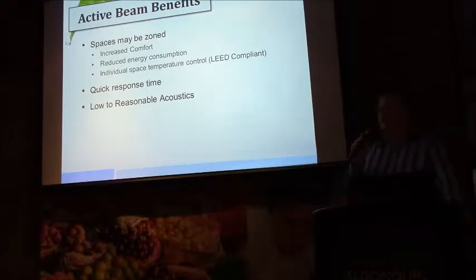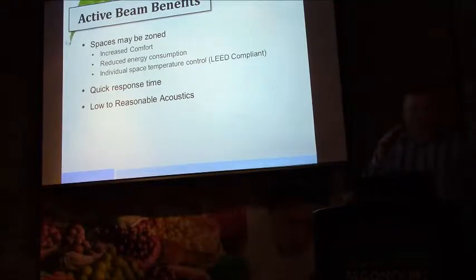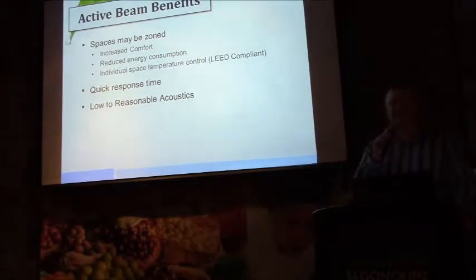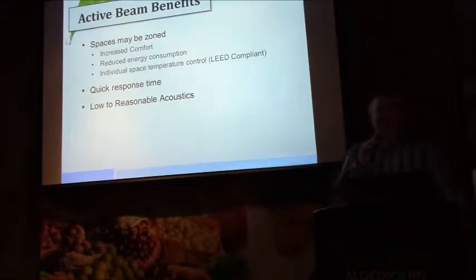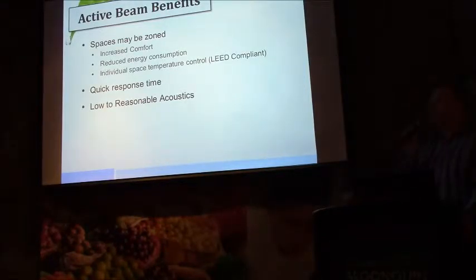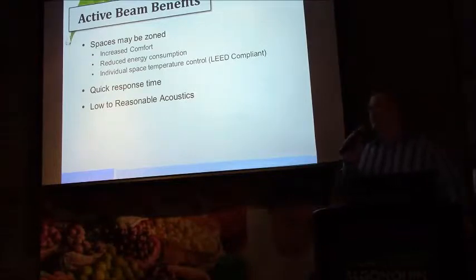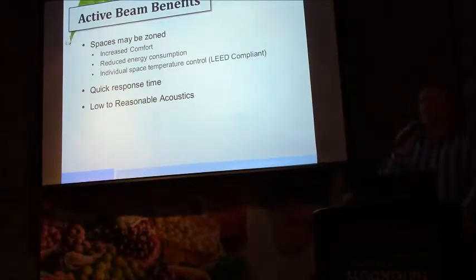And so it's been observed on other projects whereby a competitor came and offered a shorter coil because the capacity of the beam was suitable to accomplish that. But the design criteria of the space was such that the acoustic content was driving the length of the beam. And an 8-foot beam was actually required with smaller nozzles to deliver the spectral content for the acoustic engineer to solve the acoustics in the space, given that it was a recording studio and a performing arts school. So this value engineering attempt, which conceivably could do the job with a 4-foot coil, that wasn't the issue.